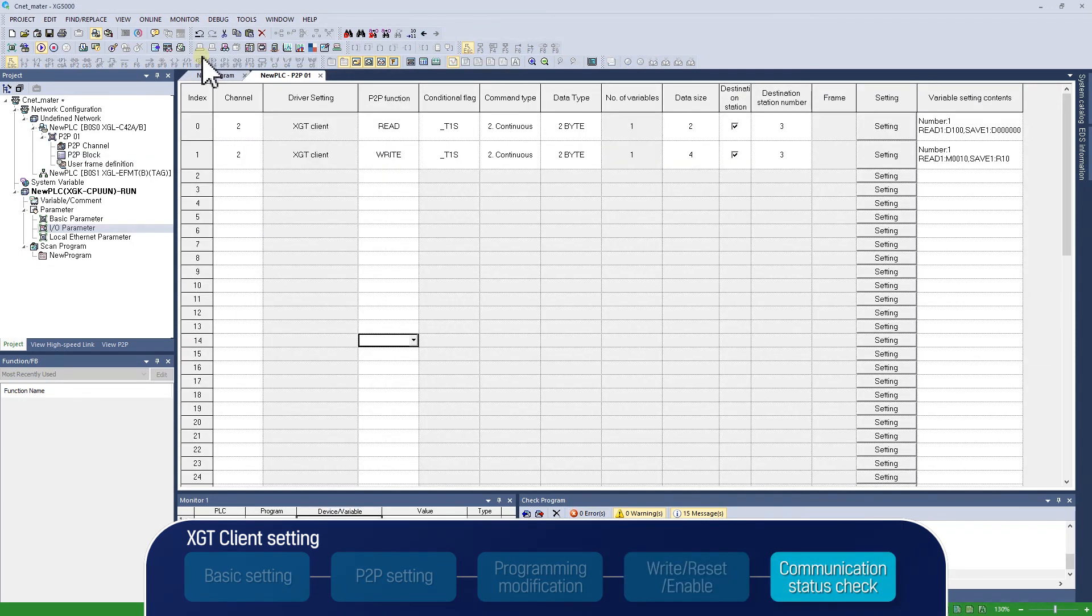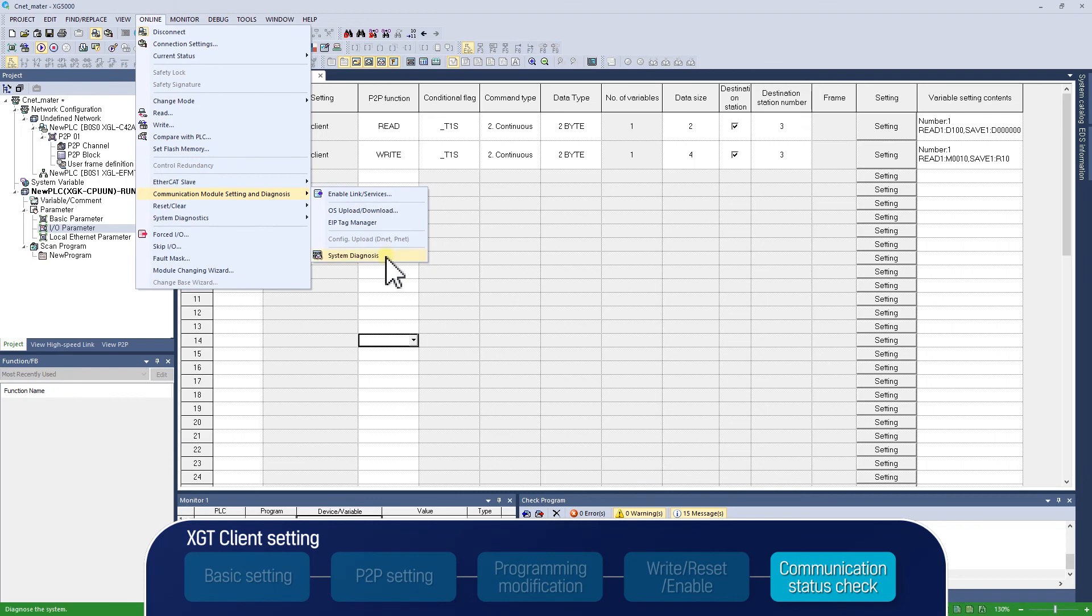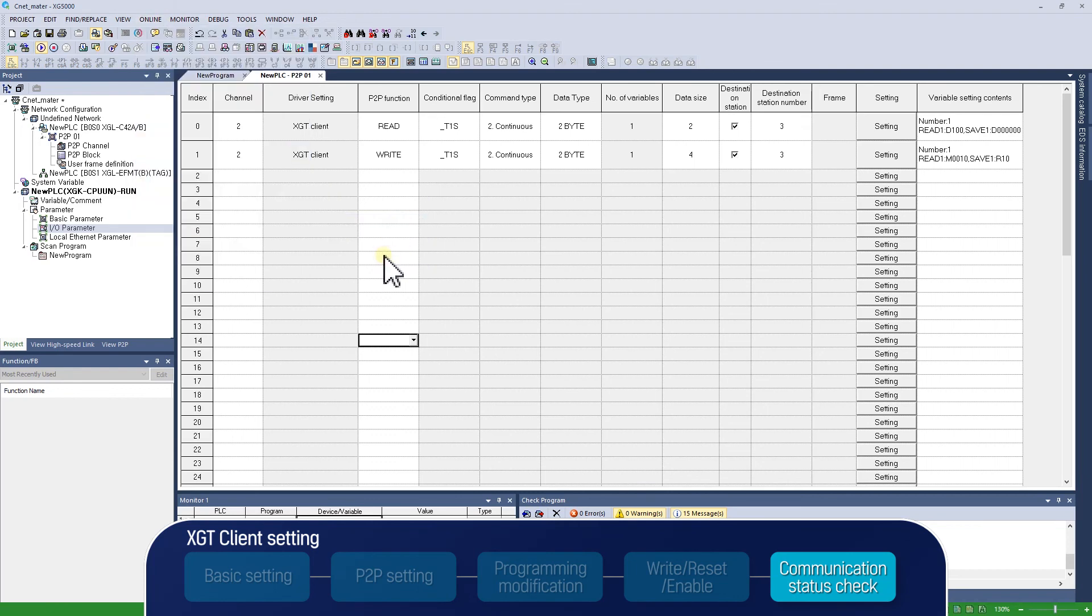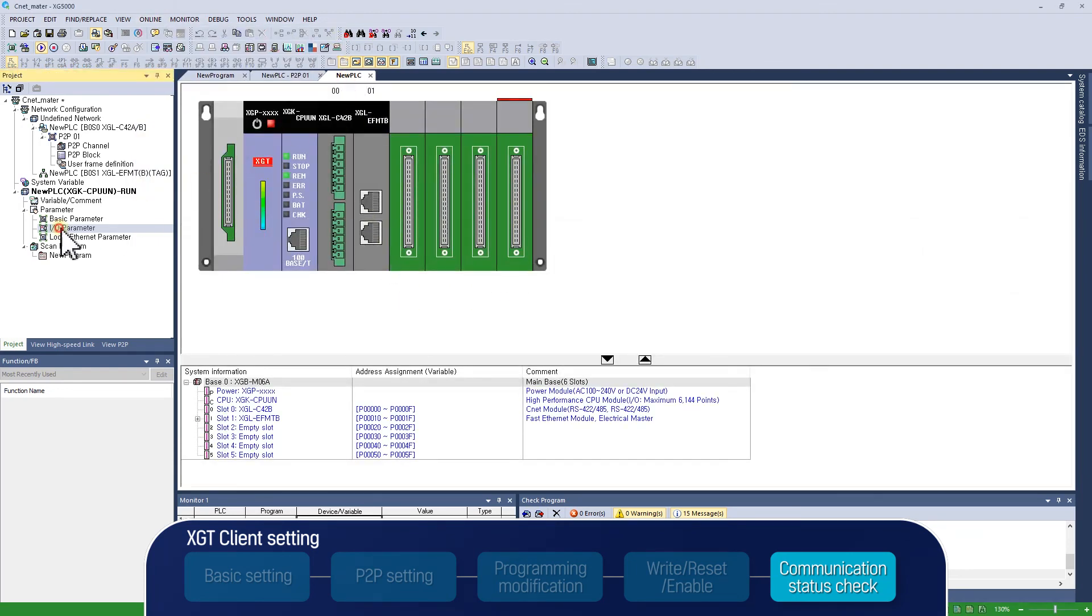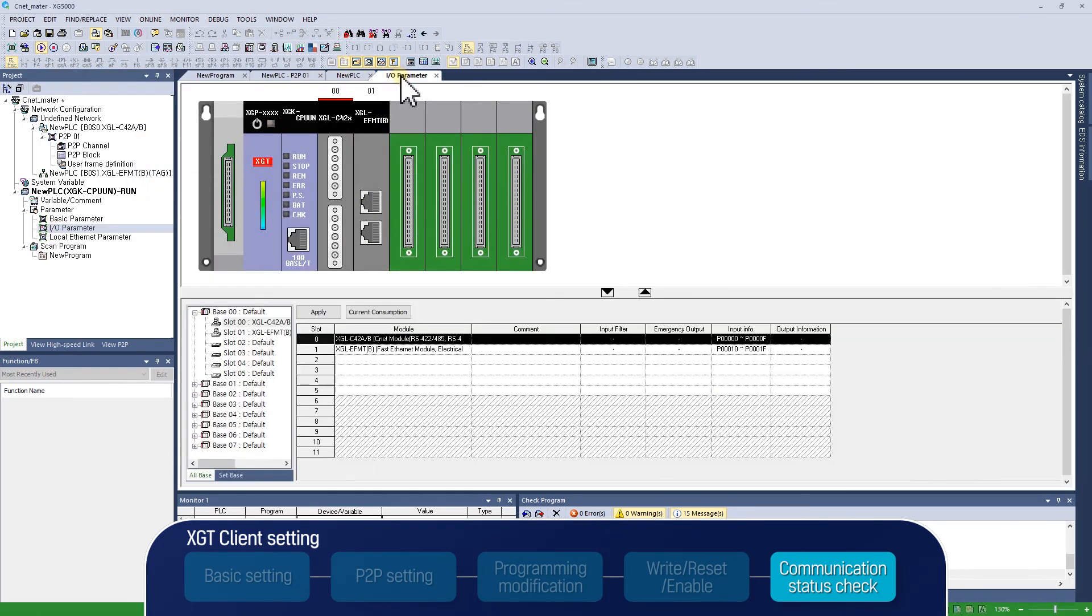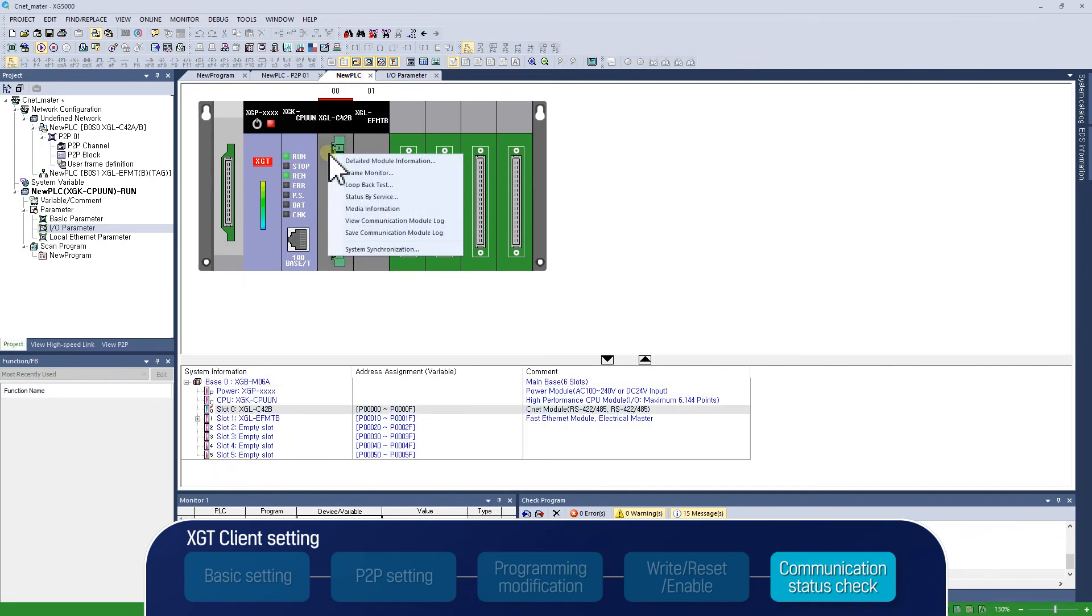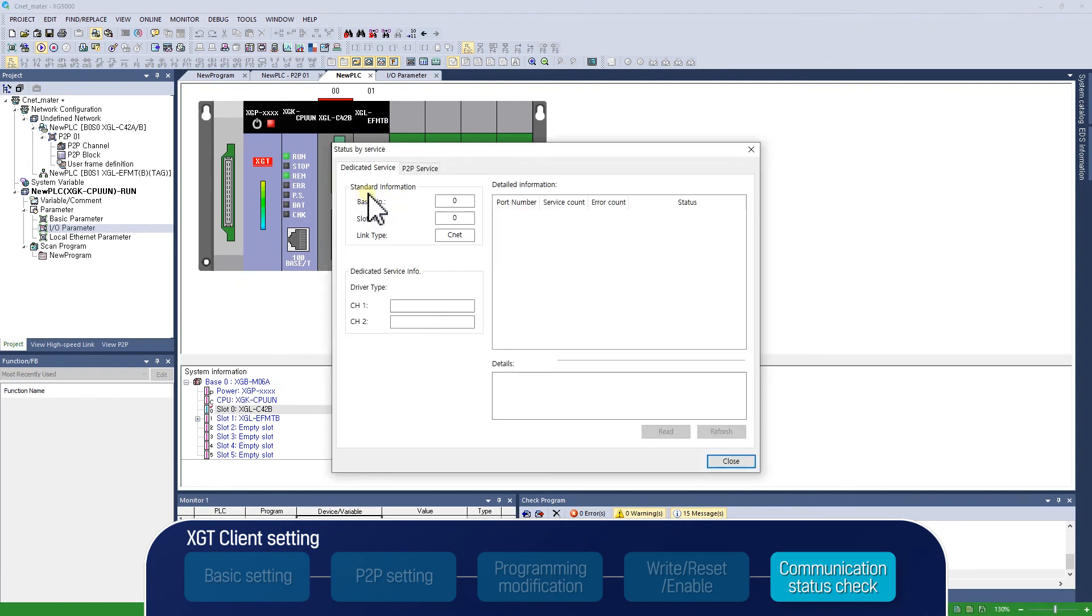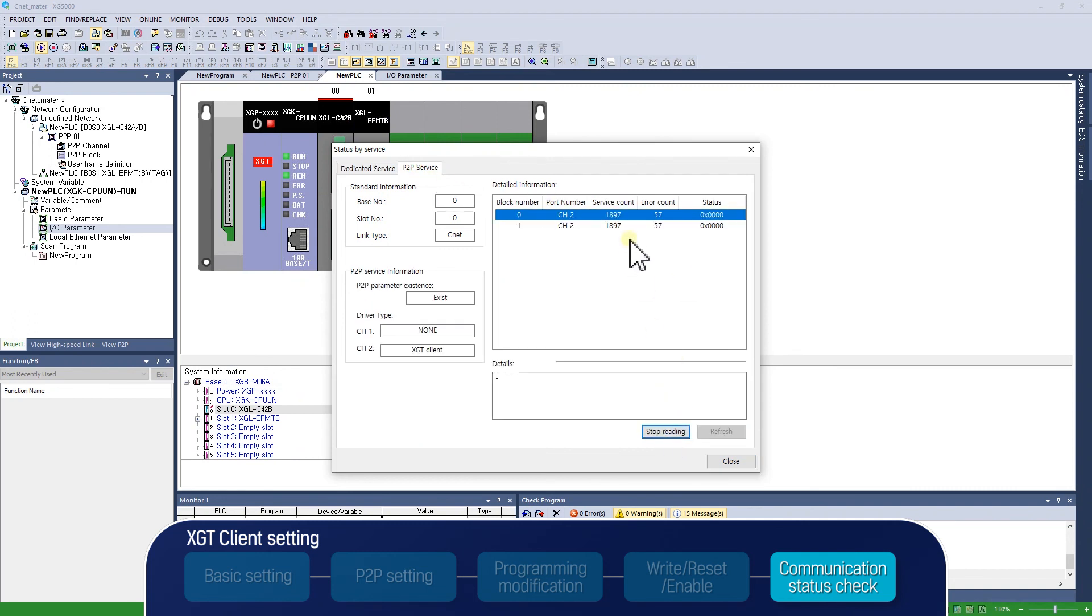Now, let's find out the communication status. Select Online, Communication Module Setting and Diagnosis, System Diagnosis. Right-click on the module to find the communication status and select Status by Service. As P2P communication is applied, choose P2P Service tab, and Read will show you service count and error count.